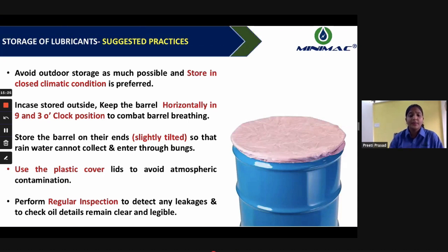And if it is kept in a vertical position, it should be tilted a little, so that water does not collect at the bung area. The basic thing is to cover the barrel with a plastic cover, so that particles and moisture do not enter the bungs and affect your oil. And regular inspection is suggested, to detect any leakages or any chance that the lubricants are leaking out of the barrels. So this is the storage of lubricant.